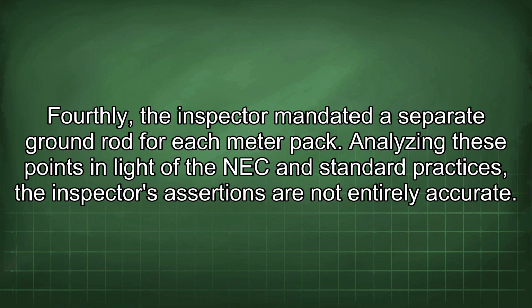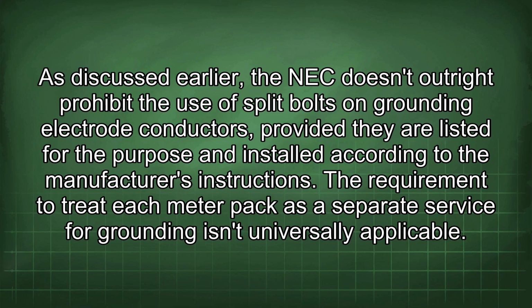Analyzing these points in light of the NEC and standard practices, the inspector's assertions are not entirely accurate. As discussed earlier, the NEC doesn't outright prohibit the use of split bolts on grounding electrode conductors, provided they are listed for the purpose and installed according to the manufacturer's instructions.